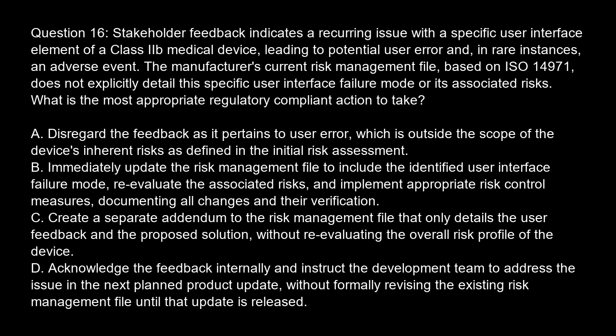Option A. Disregard the feedback as it pertains to user error, which is outside the scope of the device's inherent risks as defined in the initial risk assessment. Option B. Immediately update the risk management file to include the identified user interface failure mode, reevaluate the associated risks, and implement appropriate risk control measures, documenting all changes and their verification.